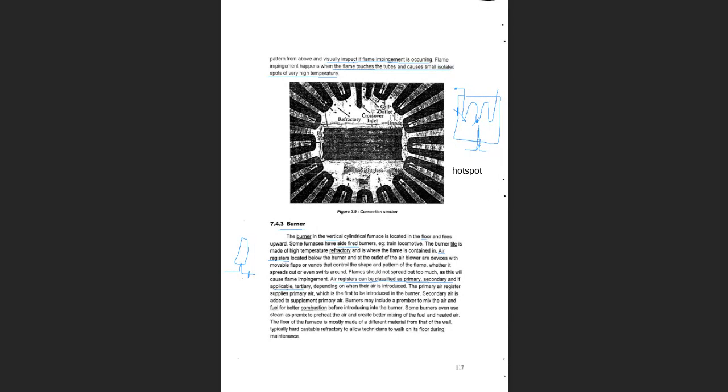طبعا إخوان, in the boilers in chapter 4 when we talk about the burners we said that there is the main burner اللي هو البرنر الرئيسي and there is the pilot burner. pilot burner اللي هو صغير جدا يا إخوان. طبعا البايلوت burner يعتبر صغير وهو عادة خلال عملية الستارت اب. جميل. usually you start up the furnace by igniting the pilot burner. هذا البايلوت burner الصغير وموجود داخل البرنر الكبير, وعملية التشغيل بعض الأحيان ممكن تكون يدوية.